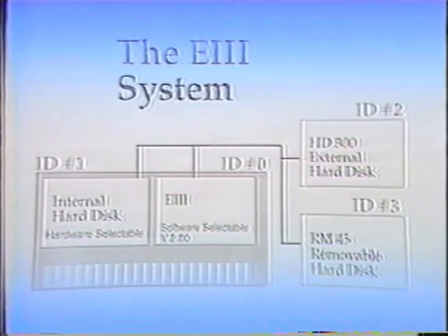This diagram represents one E3 system. It basically consists of the E3 with 2 storage devices. The E3 uses the default of SCSI ID number 0, with the internal hard disk set to ID number 1. When attaching additional storage devices to the E3, they need to be set to SCSI IDs other than 0 or 1 to prevent any conflicts. Both the HD300 and the RM45 have hardware jumper blocks used for setting this address.